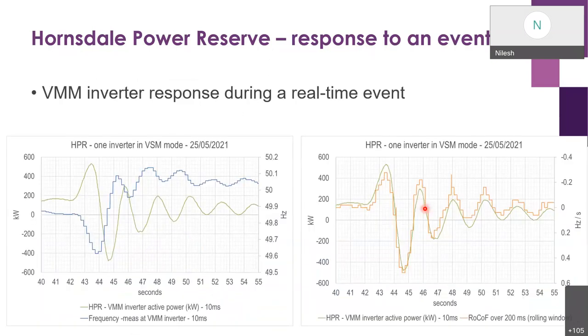I have used this slide essentially to explain a concept. On the left hand side is the same figure which you have seen in the previous slide. The blue one is the frequency, the green one is the response from the inverter. But what I attempted to do is to calculate the rate of change of frequency based on the frequency measurements. They are discrete in here because the measurements were provided to us at the time of the event. I calculated the 200 millisecond rate of change of frequency, the average rolling window. Again, one of many approaches to calculate the rate of change of frequency.